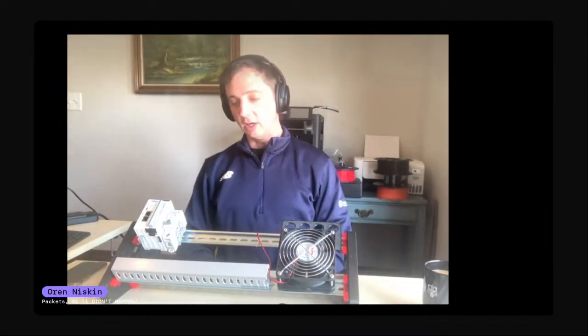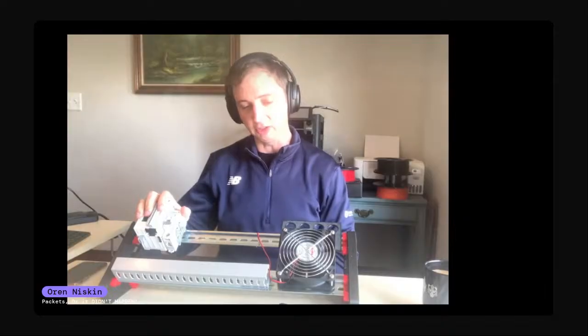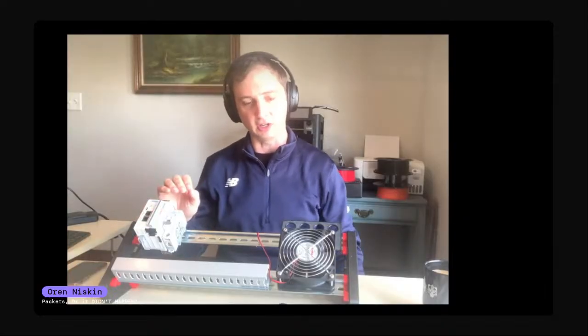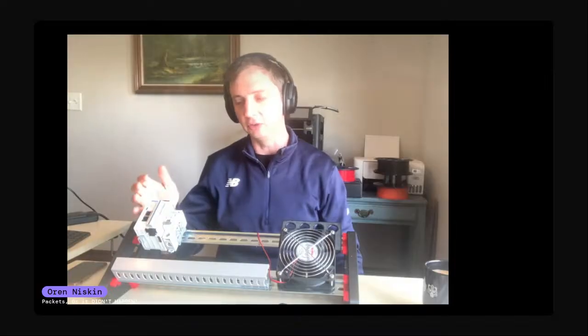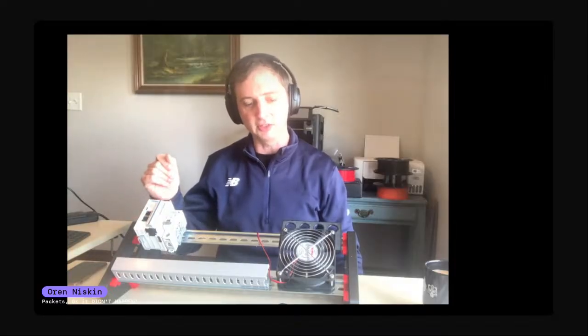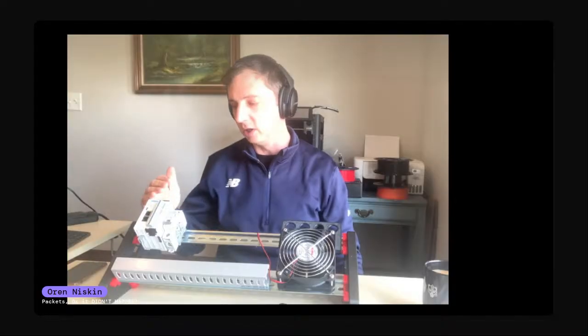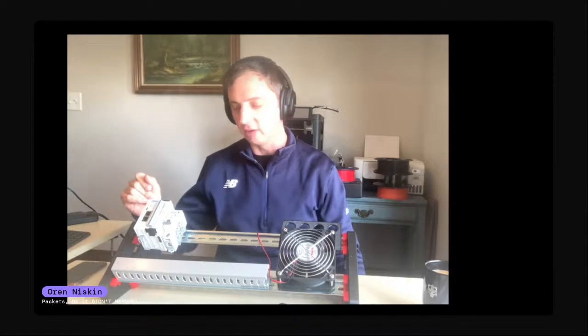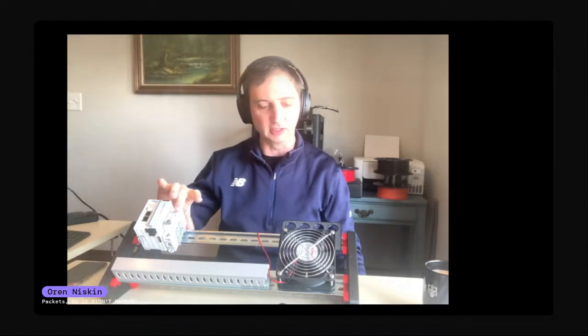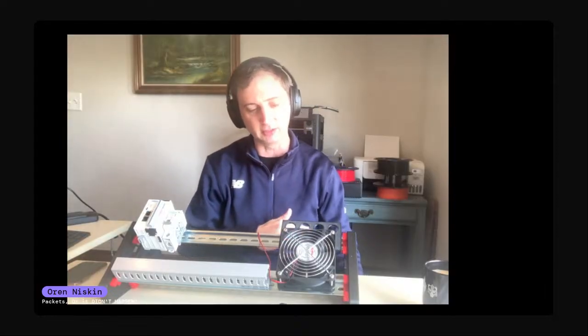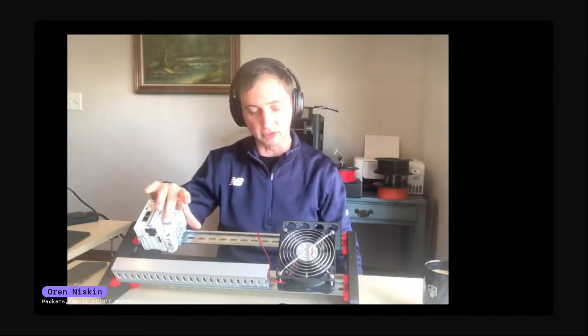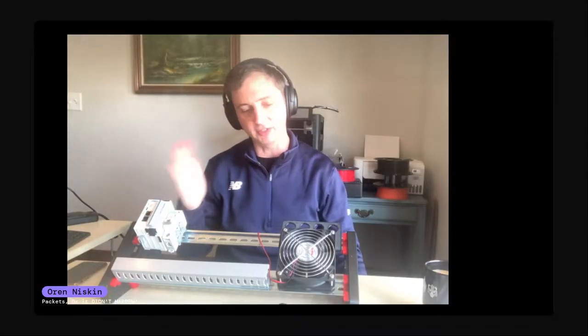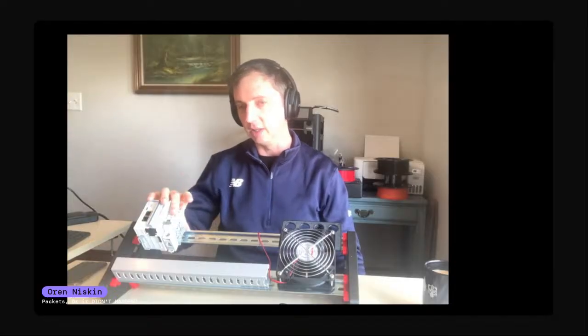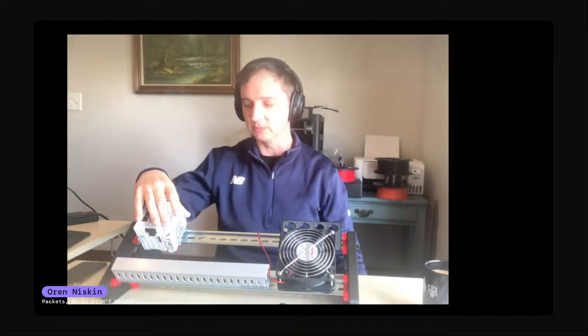To protect the PLC, it's better to use some kind of fuse. Fast fuses are really fast — the second the current goes above a certain limit, it blows the fuse. This circuit breaker is a little more forgiving, because a fan might spike above 5 amps briefly and come back down, and you don't want it tripping every time. So we allow it to go above 5 amps now and then, but if it stayed there long enough, it would trip.